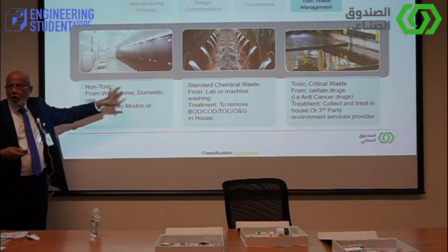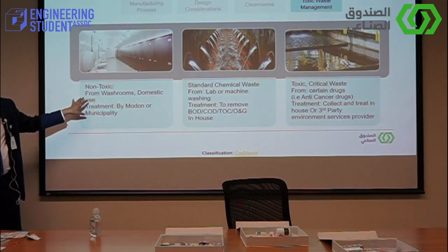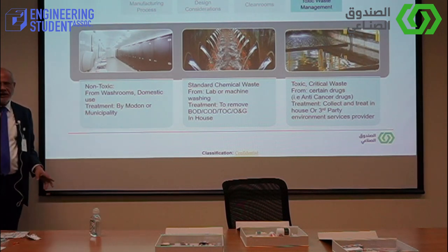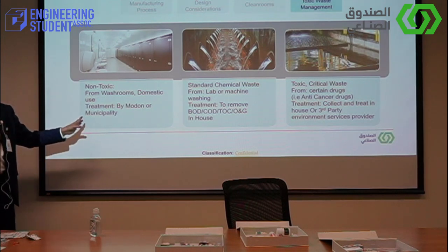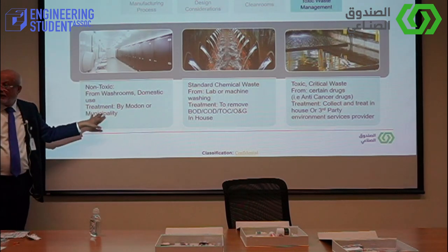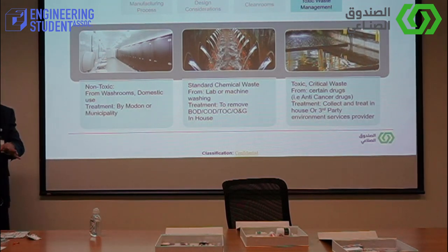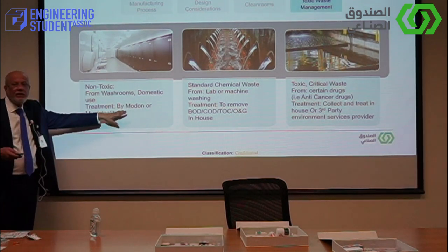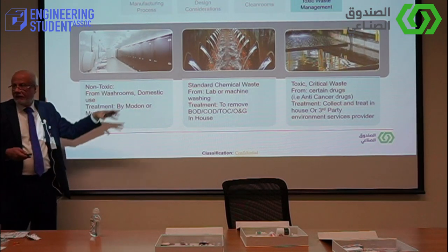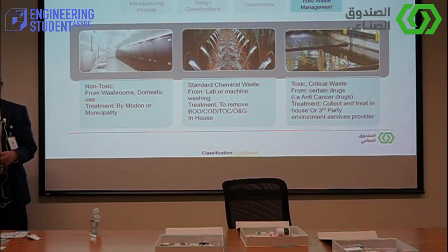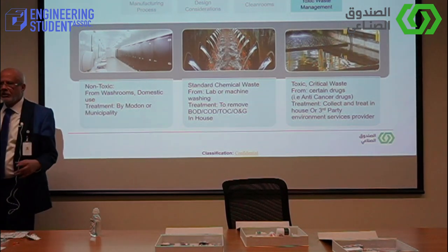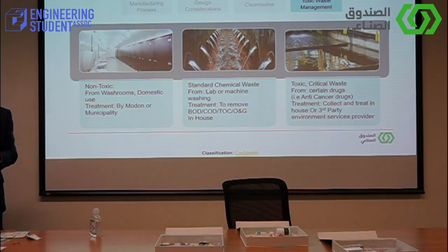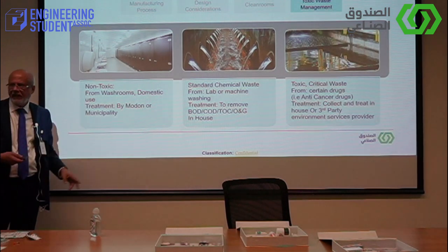Now, in a normal standard pharmaceutical factory, think of your house, everyone has a house. You have one drainage system going from the bathroom, which connects to the municipality. In this case, we have a separate drainage system going from the washrooms, bathrooms, etc., to the municipality. And then for the normal process, where I make paracetamol, diclofenac, etc., I have another one which I collect and treat for BOD and COD. I hope everyone knows what BOD is: biological oxygen demand, and chemical oxygen demand. We treat it and then we let it go.